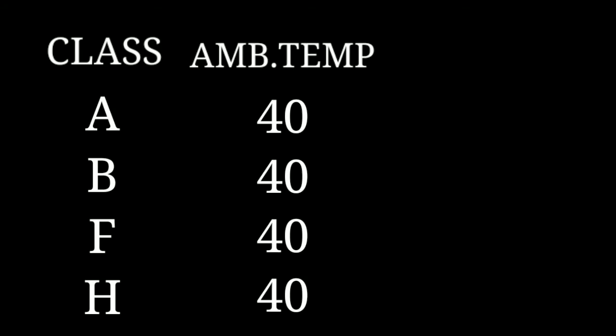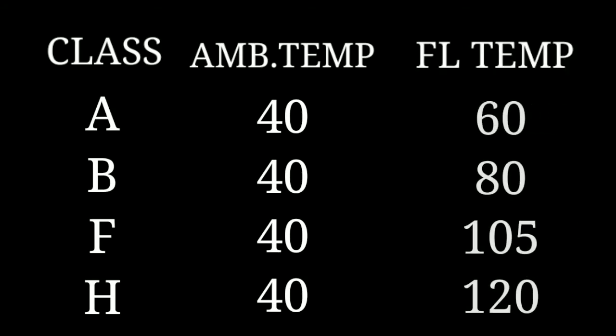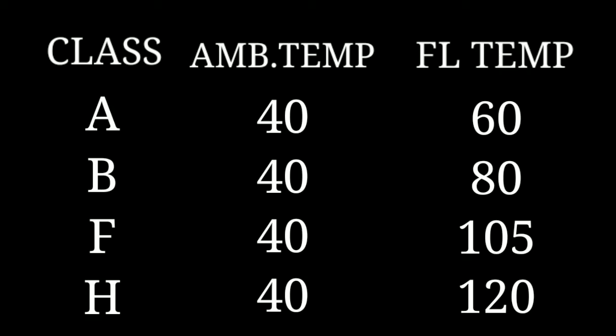All classes have an ambient temperature of 40°C. The full motor temperatures are: A class to 60°C, B class to 80°C, F class to 105°C, and H class to 120°C.